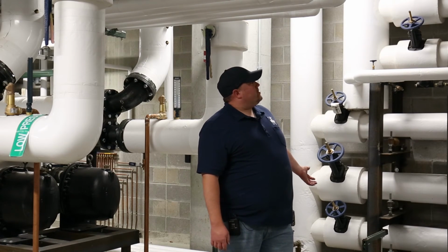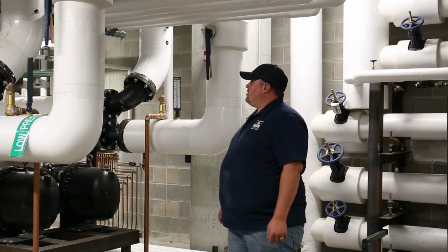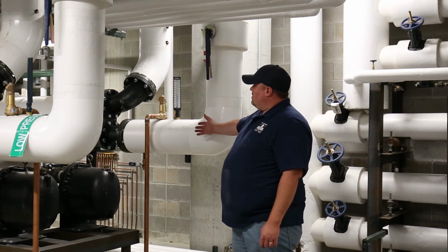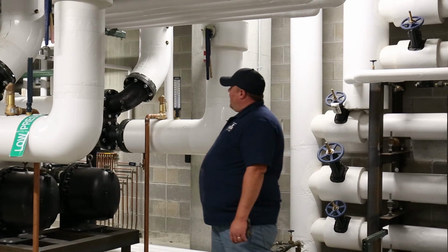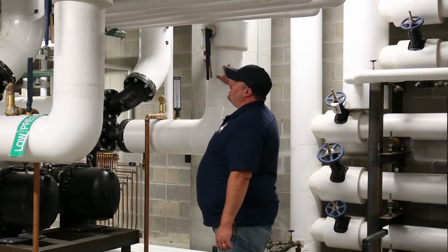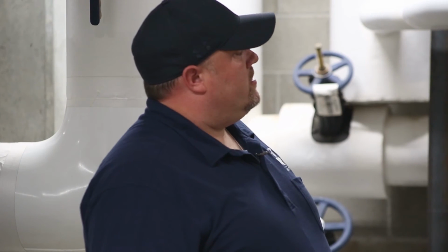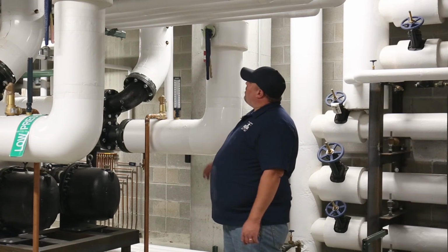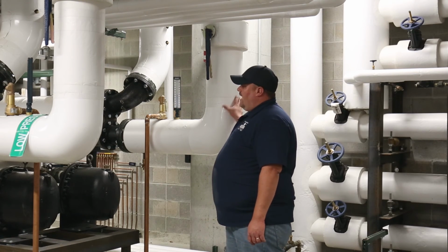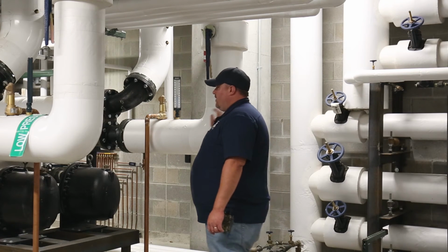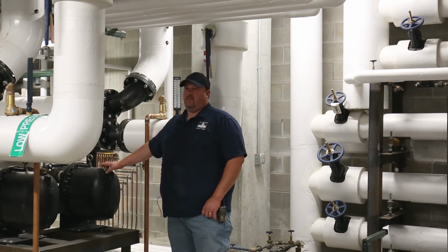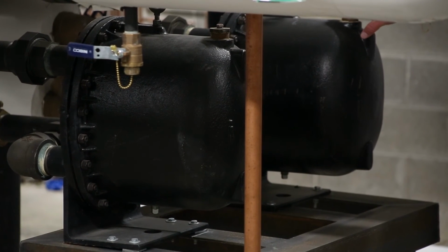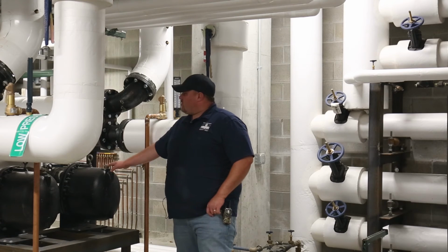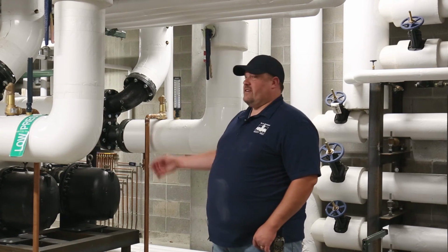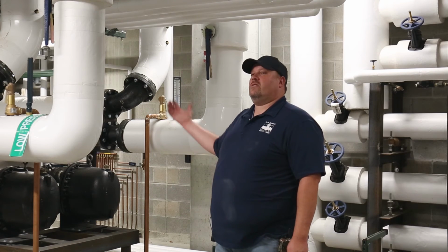Here, leaving our 1/3, 2/3 stations, the steam supplies heat to our heating hot water heat exchangers, where we have the supply and return circulate through the system. After leaving the 1/3, 2/3 stations, our steam goes and supplies the feed to our heating hot water exchangers, where the water loop circulates through, heating the water and sending it back out to the system. Here we have two steam traps. After leaving, the steam condenses down to condensate, leaves the condensate traps to our condensate receiver just past, where it gets pumped back out to the campus system.